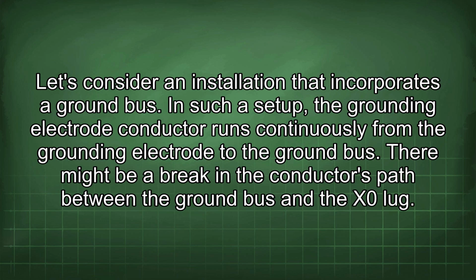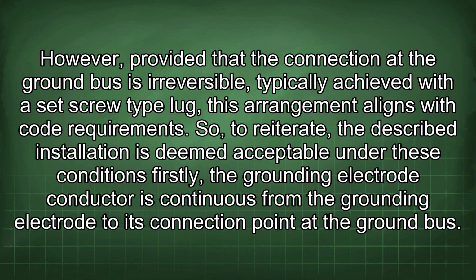Let's consider an installation that incorporates a ground bus. In such a setup, the grounding electrode conductor runs continuously from the grounding electrode to the ground bus. There might be a break in the conductor's path between the ground bus and the X0 lug. However, provided that the connection at the ground bus is irreversible, typically achieved with a set screw type lug, this arrangement aligns with code requirements. So, to reiterate, the described installation is deemed acceptable under these conditions.